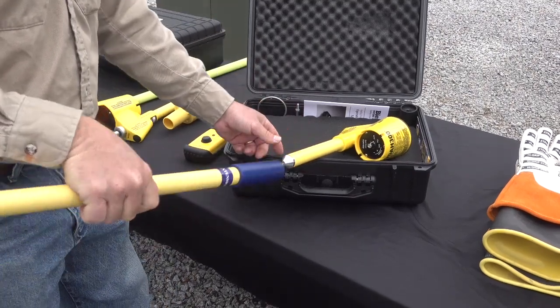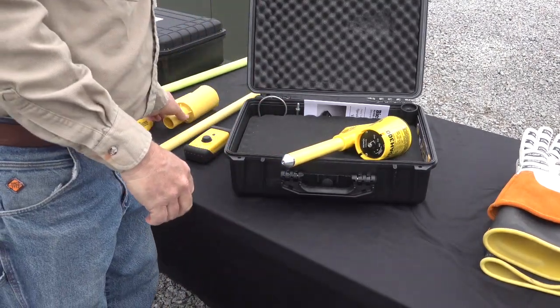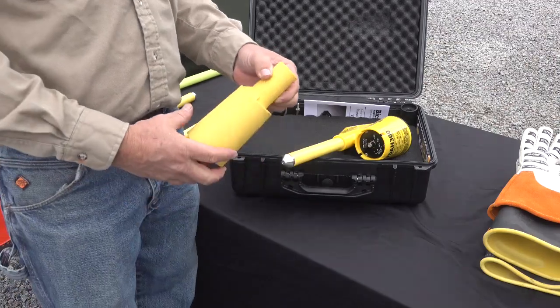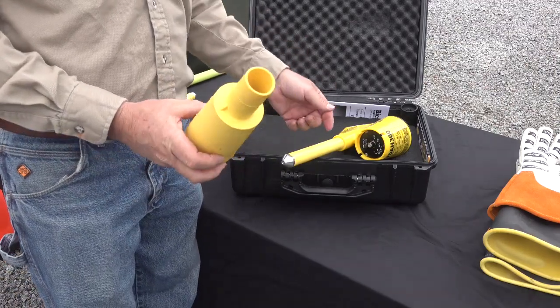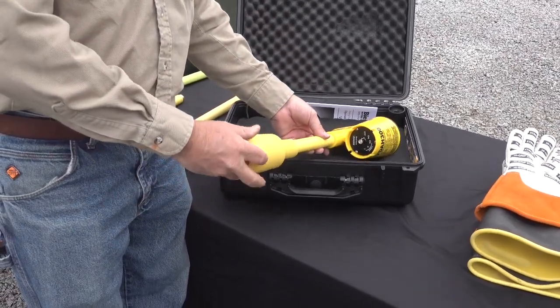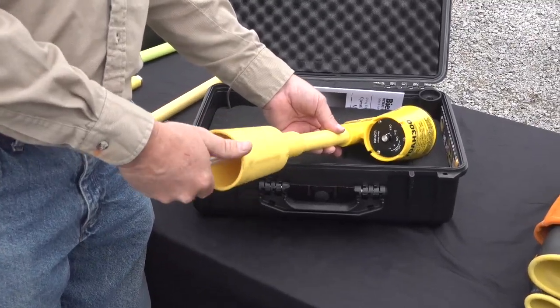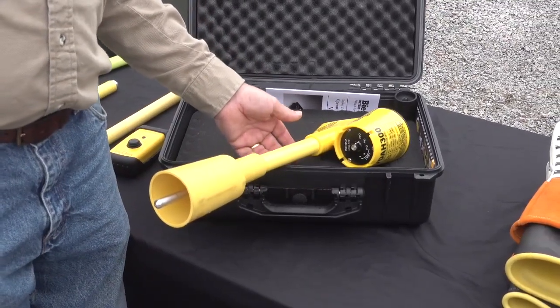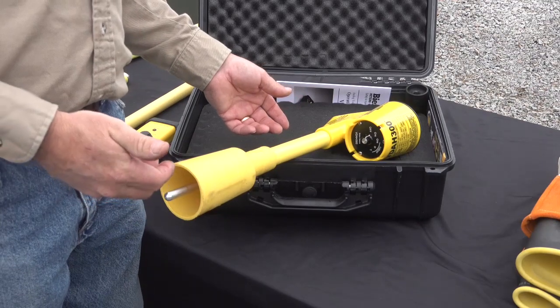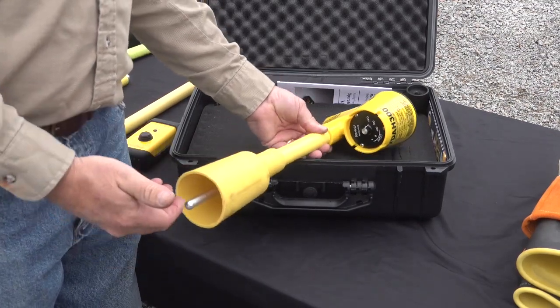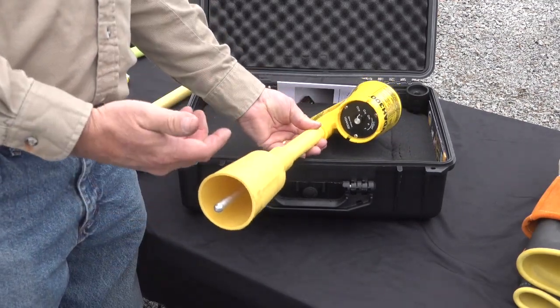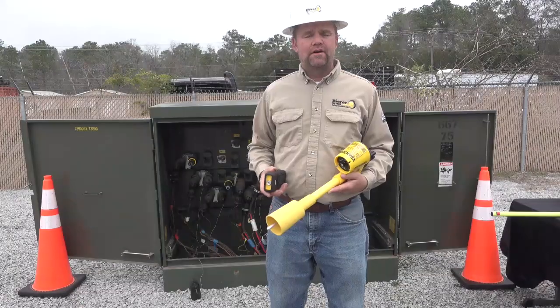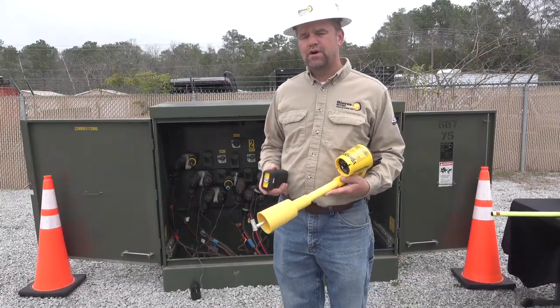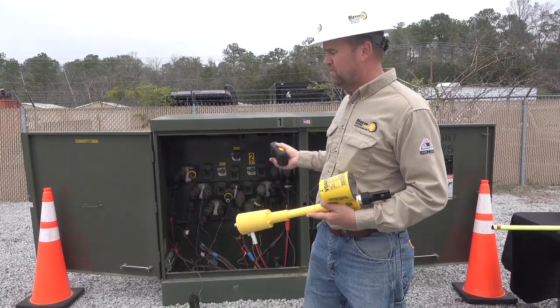Also in underground applications, we have bushing adapters. We have a small interface and large interface bushing adapter. Again, a 1/4 20 thread threads onto the end of the probe, and again this is used in situations where you may pull an elbow on a feed through, and you actually insert this into that bushing to take your nominal voltage.